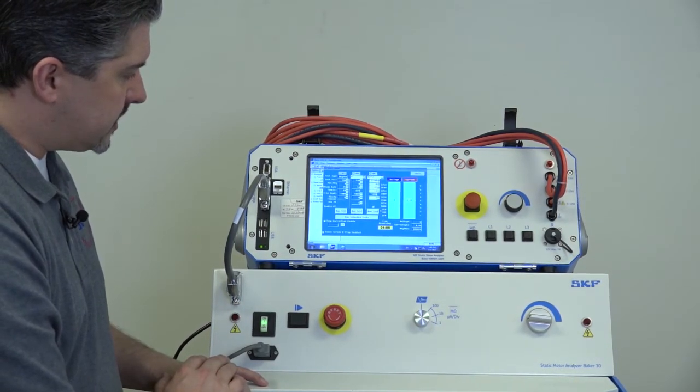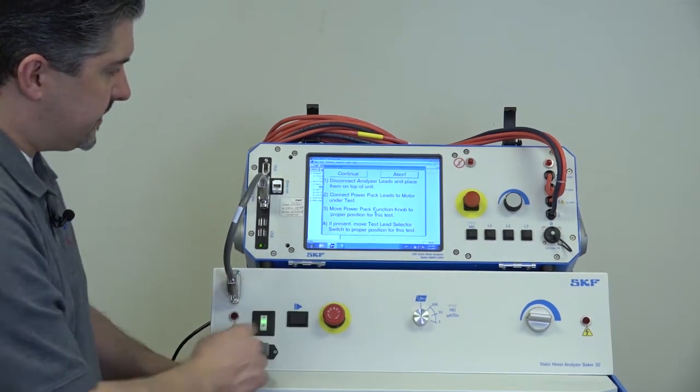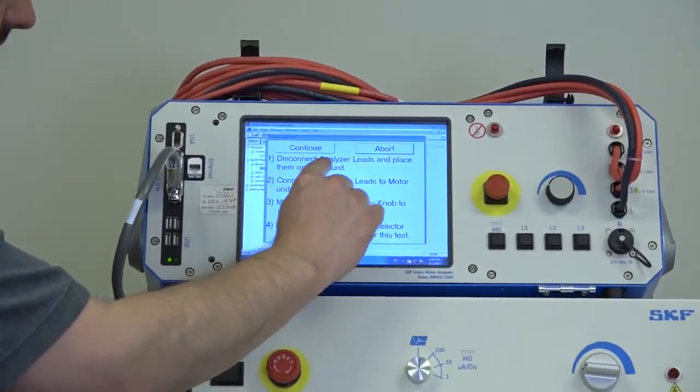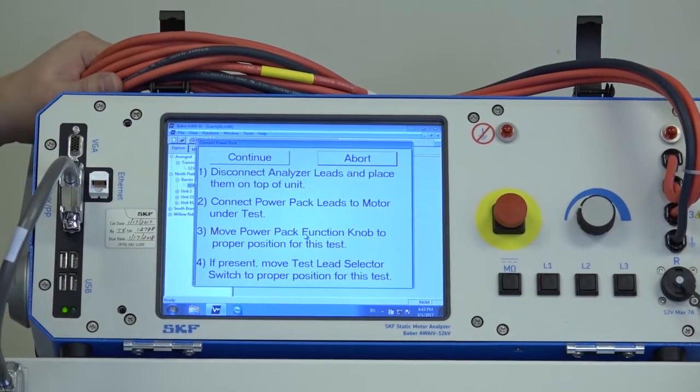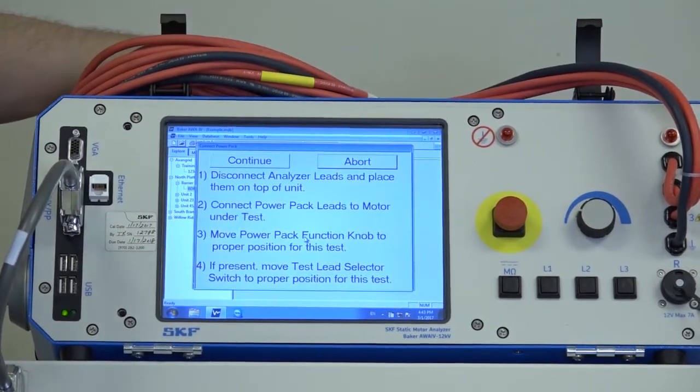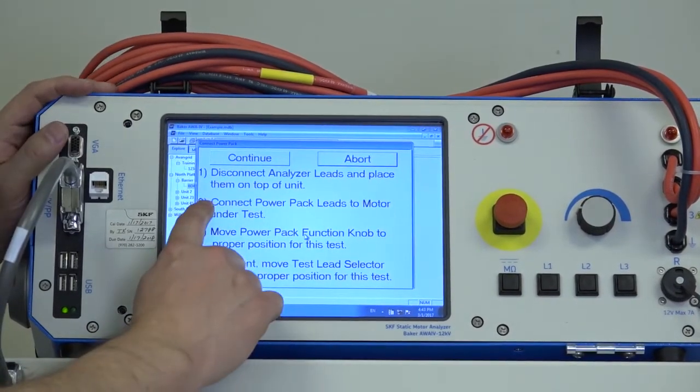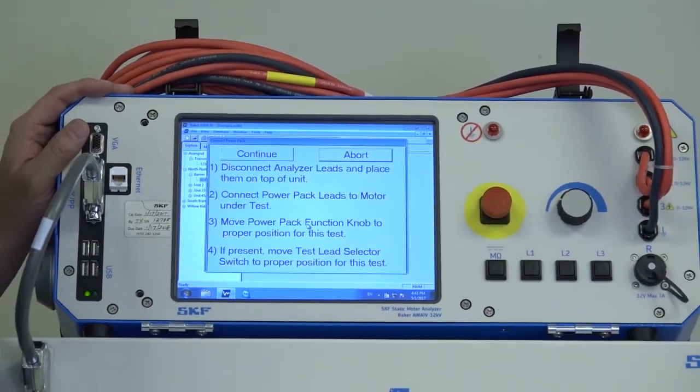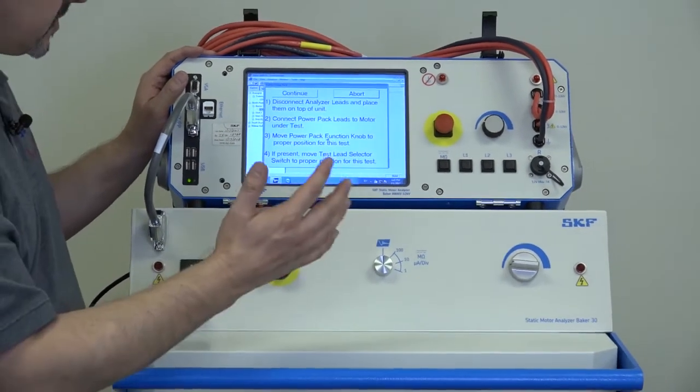When you're ready to initiate the test, you can hit run test, and then you have an on-screen set of instructions. Number one says disconnect the analyzer leads and place them on top of the unit. So that's the normal AWA leads. When we're using the PowerPak, we don't use these leads. Put them up on the tester so we don't get confused about what we're connecting. Step two, connect PowerPak leads to the load on test. So the PowerPak leads that I showed you earlier that come out of the bottom of the unit will connect to our load, to our motor, our circuit.